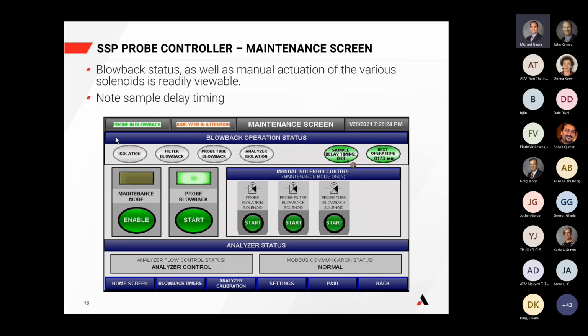And what we do is we tell the analyzer to stay in maintenance mode while the sample flow is returned back to the analyzer and through any of the sample handling components after a blowback. And we do that to ensure that the end user doesn't get some random reading of, let's say, 0 H2S and SO2, because effectively all it's seeing is the instrument air that was used to clear the filter and the probe during the blowback. So we purposely introduce a delay there. And that's what you can see here, that we've got a countdown going.